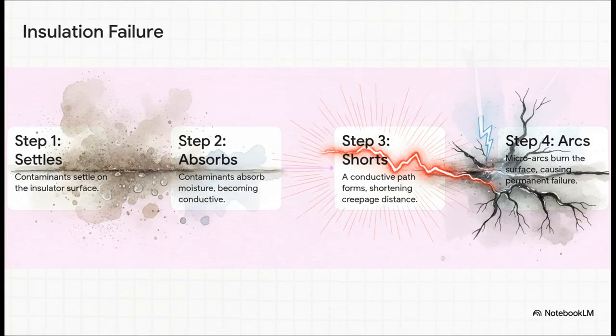Here's the chain reaction of disaster, step by step. First, dust and grime settle on an insulator. Then it gets damp, creating a conductive shortcut for the electricity, a new, much shorter creepage path. Finally, tiny sparks called microarcs start to form across this new path. These sparks literally burn the surface of the insulator, leaving behind carbon tracks. And since carbon is conductive, you've now created a permanent burned-in failure that will only get worse over time.